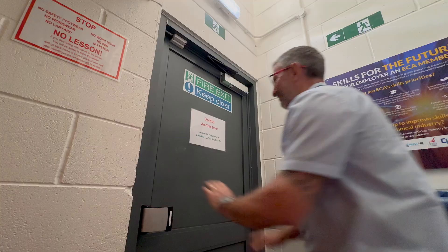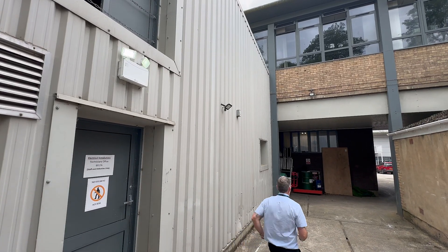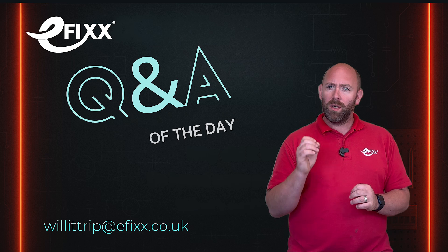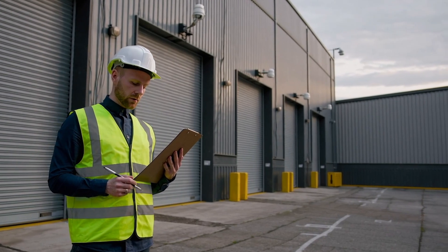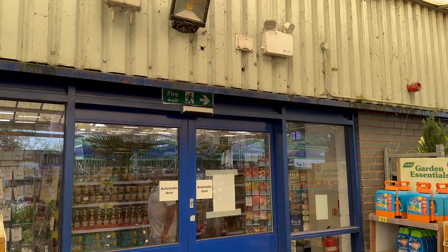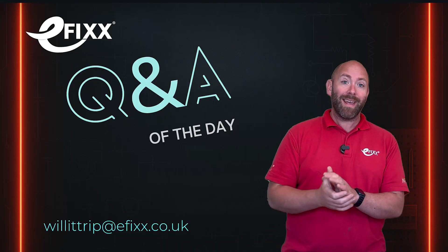So if people exit the building but still have a way to go before they're actually safe, they need to keep that journey illuminated. Here's the key part: you don't install emergency lights just because the regs say so — you install them because a risk assessment has identified the need. A fire exit that opens into a dark service yard, a retail garden centre, or a multi-level stairwell — those are examples where emergency lighting outside is essential.